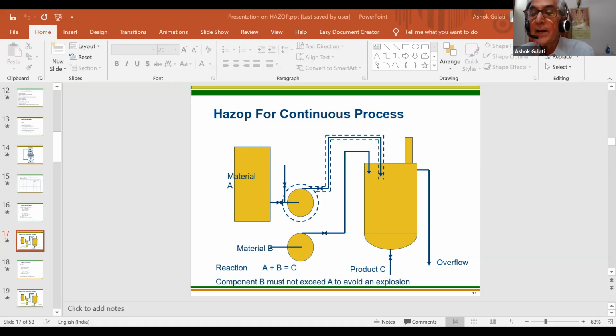Pump is not working, very right, and valve is closed, very correct. That can also happen. Pump is not working due to maybe electrical failure or mechanical failure. Pump can be seized: the pump was running, suddenly got seized. Mechanical failure inside, for example, the impeller inside gets dislodged and it gets seized. So flow comes to 0 immediately. Or electricity gets cut off and due to some fault in the electrical line, the pump stops. That can also be there.